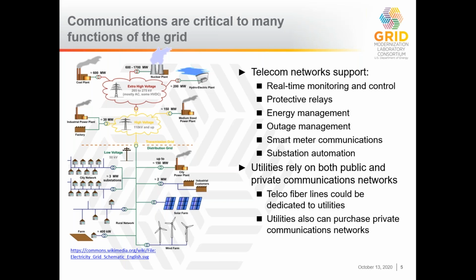On a very basic level, we tend to separate protection from metering. If there's a type of measurement meant to take an action locally, like protective relays would take, you'll focus on sending that data within the controlled boundary needed for protection. But for things like smart meter communications, you want those to go up to the higher level and billing sent back to the right people. So we tend to separate protection networks from the other networks used in the system.